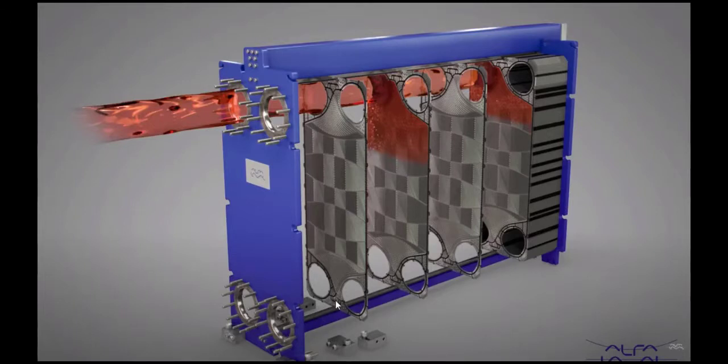This same gasket pattern is used for the other fluid, permitting this fluid access to the other side of the plate. The result is each plate has on one side one fluid and on the other side the other fluid, traveling counter-currently to each other. Counter-current flow is one of the reasons gasketed plate heat exchangers are superior to other types of heat exchanger. We mentioned the importance of fluid distribution across the plate earlier.